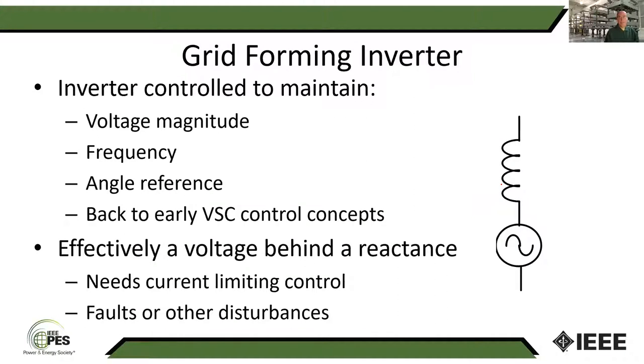and again, in some ways this is going back to older concepts for voltage source converters. When you think about a motor drive, the inverter that faces the induction machine is acting as a grid forming inverter. We've got an inverter that's controlled to maintain voltage magnitude, and now we have something that's setting frequency. In some cases, we can have multiple converters that are sharing frequency control. In other cases, you may have one inverter that's the grid forming inverter and everybody else synchronizes off that, if you've got one that's bigger than the others. And then you may even have something that's setting an angle reference for the others.